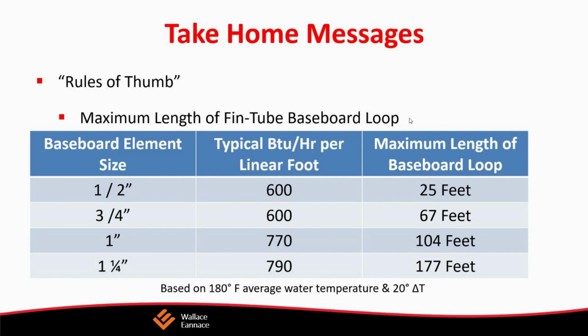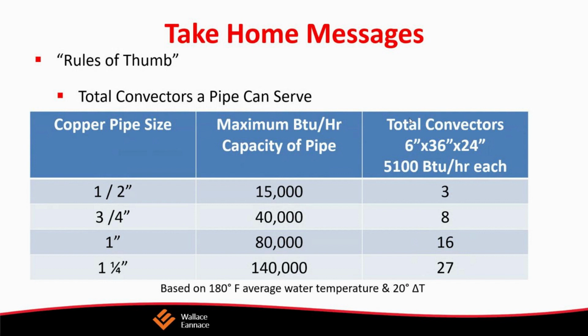The next thing is the maximum flow rate that you can get through pipe size. Again, half inch is 1.5 GPM, 4 gallons a minute through 3/4, 8 gallons a minute through 1 inch, and 14 gallons a minute for 1 1/4 inches. Pump head. How do we calculate the pump head? Measure the longest run in feet, add 50% of that number, and multiply that number by 0.04, and that gives you the pump head. That's the quickest and easiest way to calculate how much head you need in your pumps.